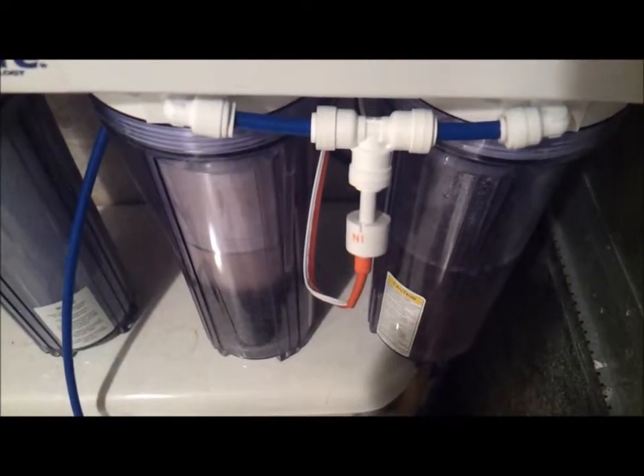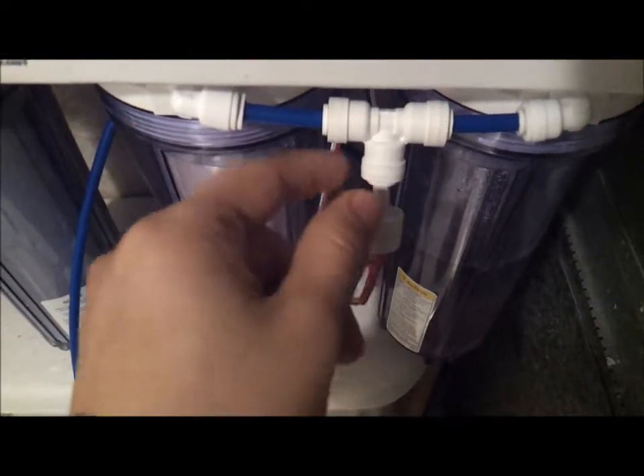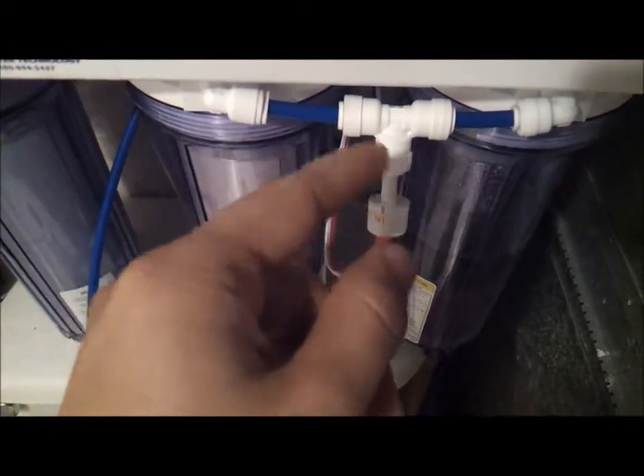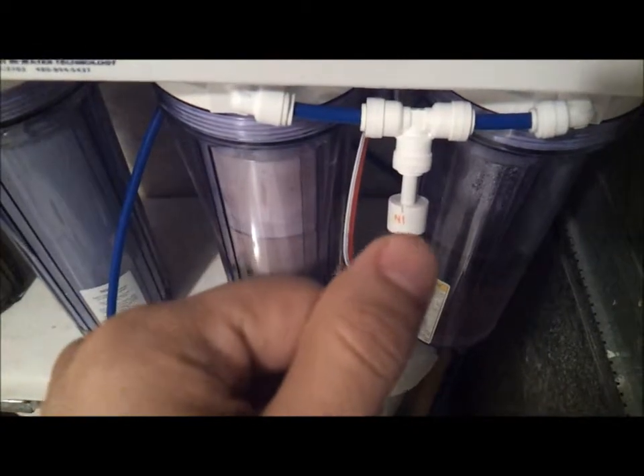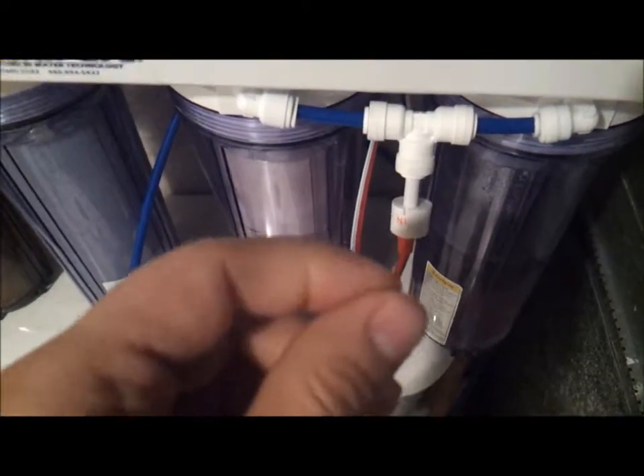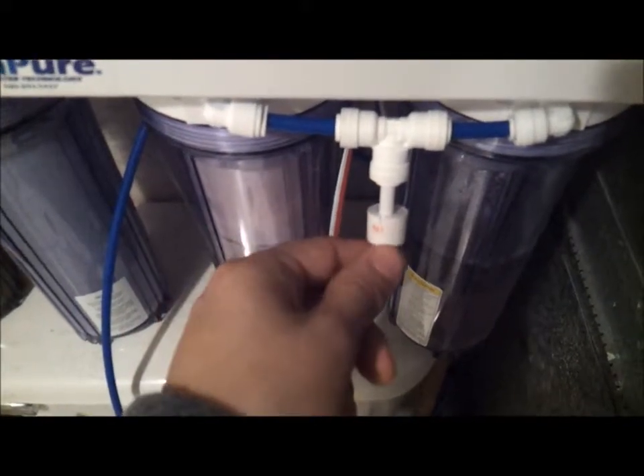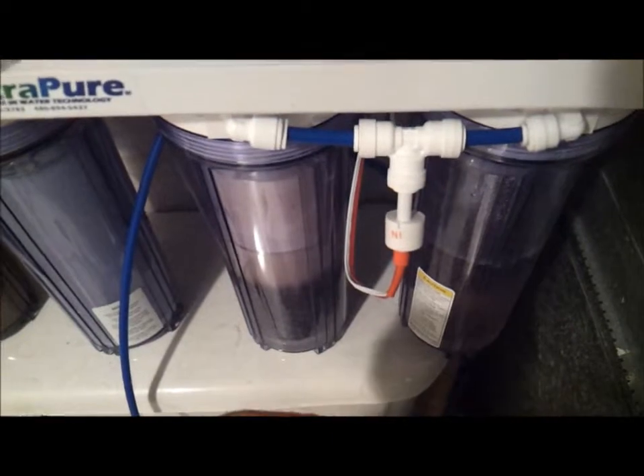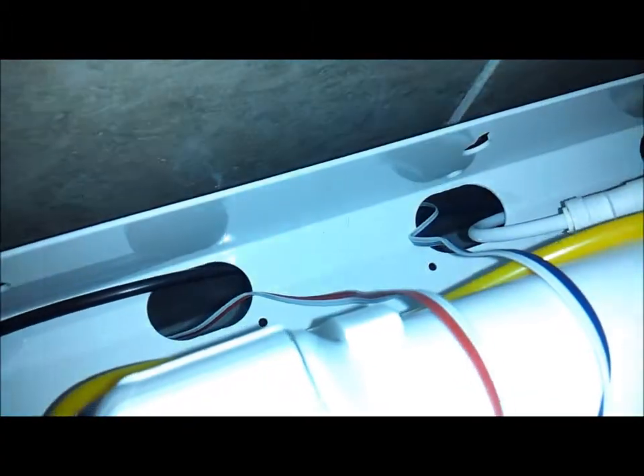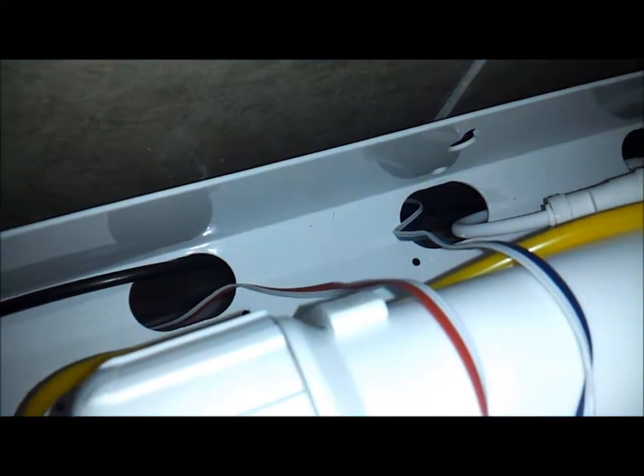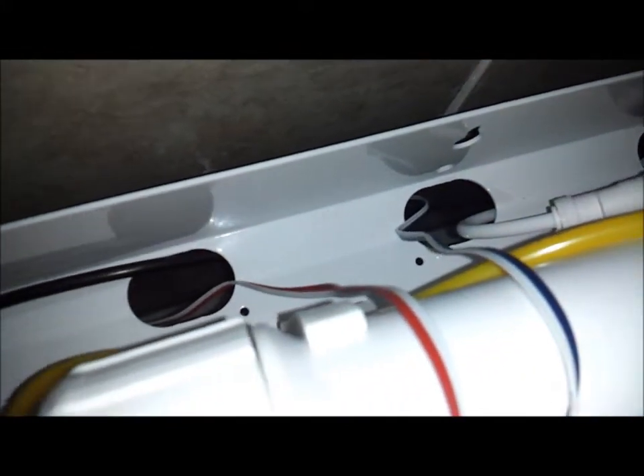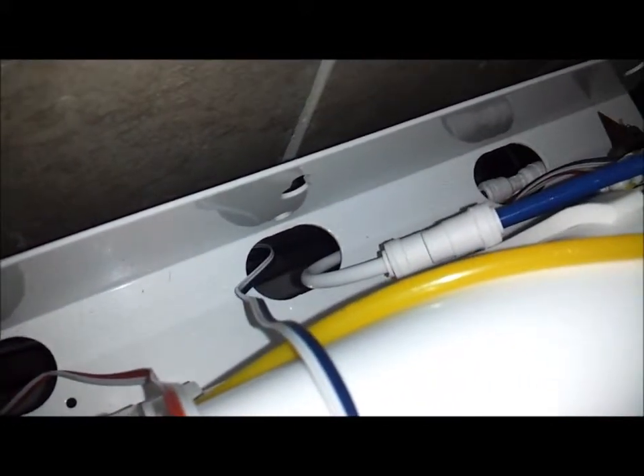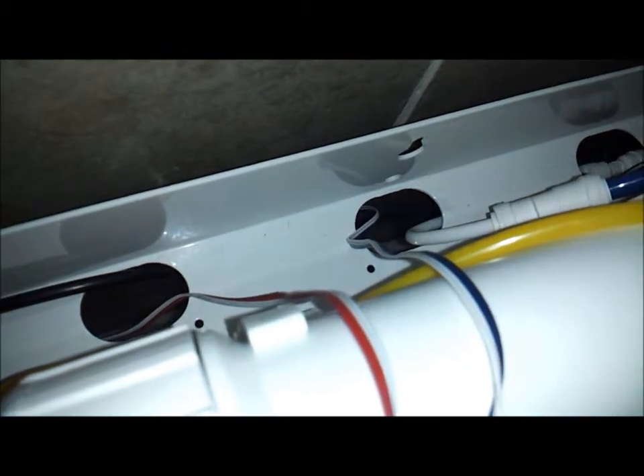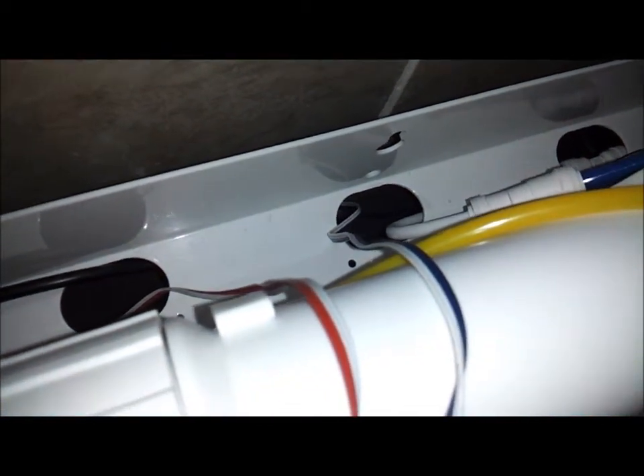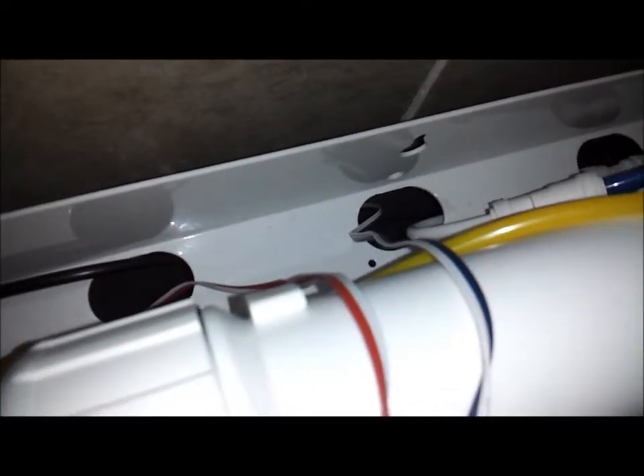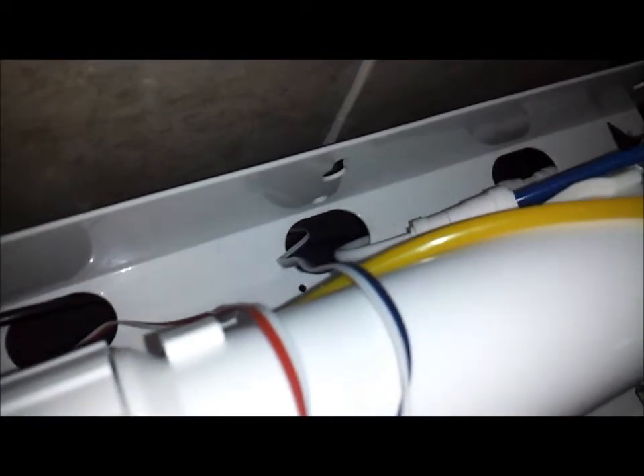When you move your probes, do not take the probe from the T - take out the entire T, because if you don't, you'll be very pissed off since you'll have to spend $50-60 to replace it. You could take that T from one of the holes located in the back of the unit, as you can see right there, and place the TDS probe into a desired location where you'll monitor your TDS from.